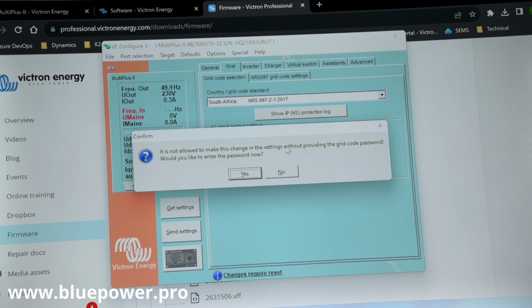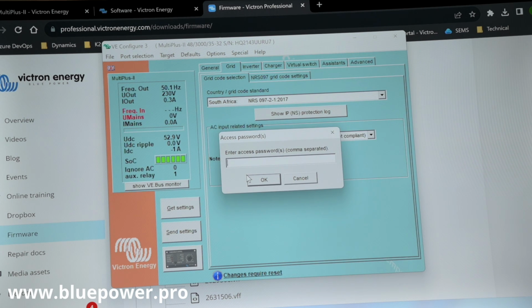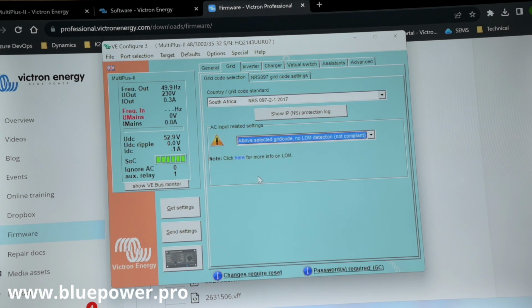So let's say you have changed it, or it's a requirement to change it, it's also going to ask you to enter the grid code password. Over here we can say yes. That password is not available on the internet or from your distributor, but it is the standard grid code password, and it has been for the last 6 years. It will always be that password. Is this information in the book? No. On the internet maybe not, but it's generally not a requirement to change any of this. But if you've got a generator, or you selected the wrong grid code and you want to change it back to South Africa, then you are going to require the access password. That password is only to change the grid settings on the Victron inverter.